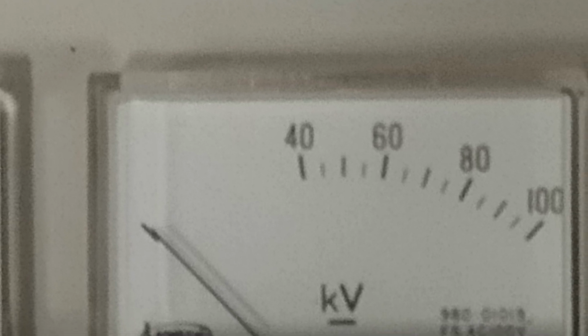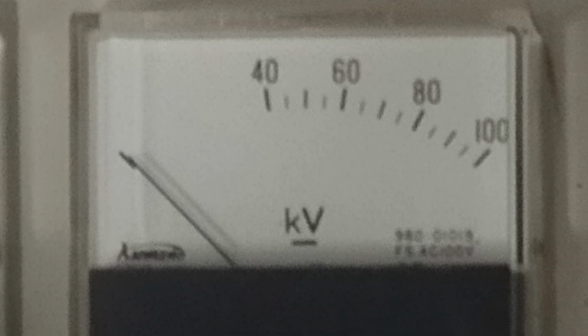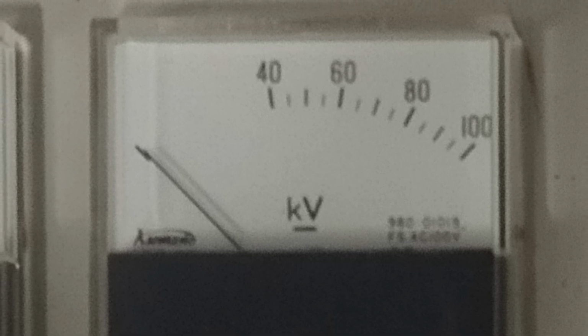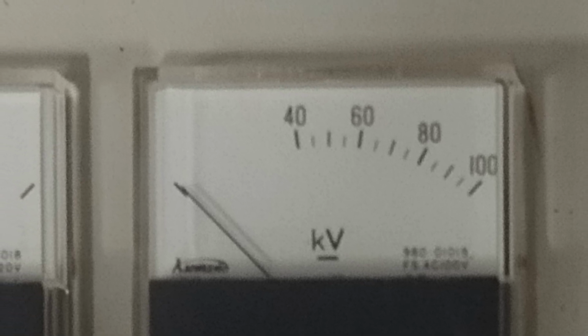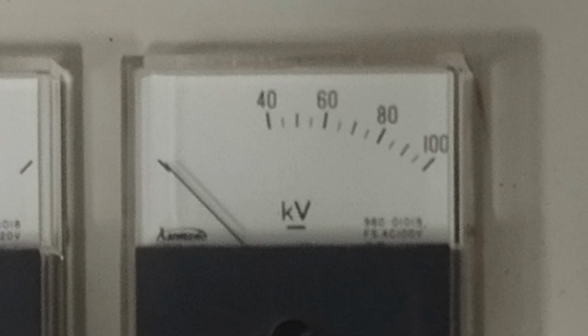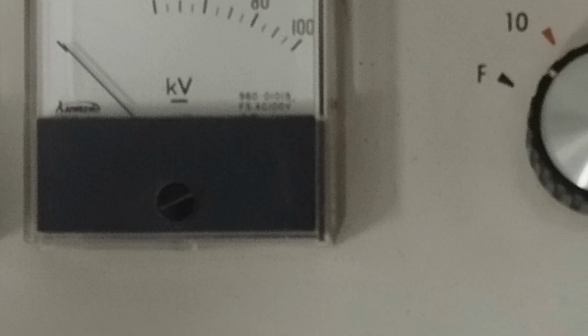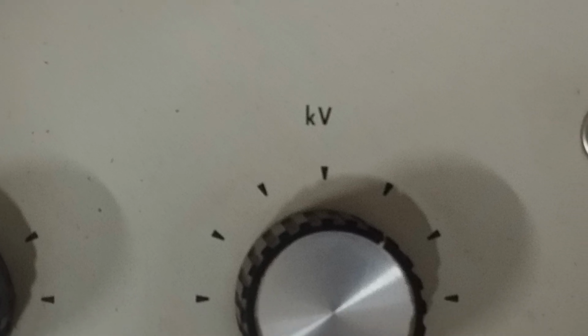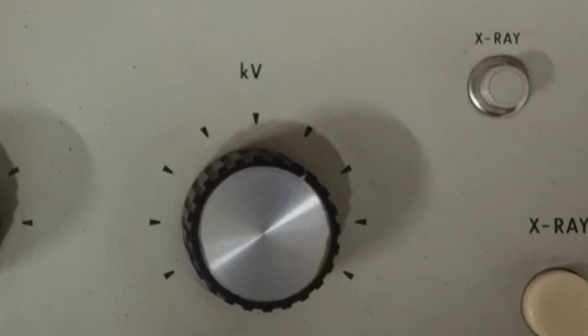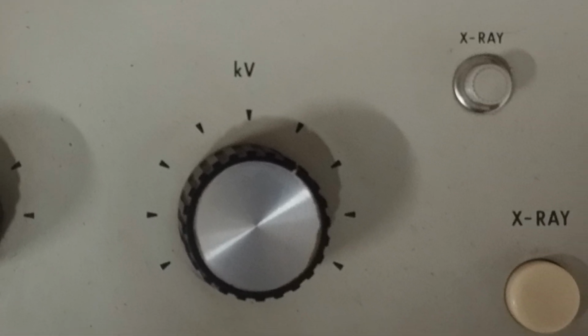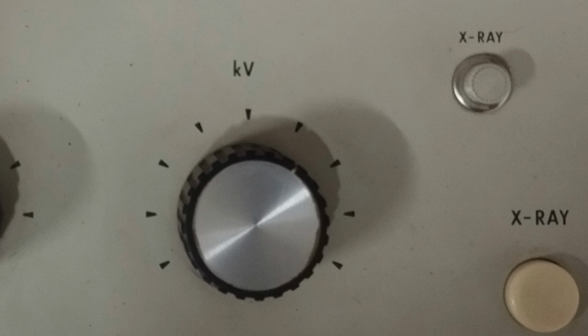Depending on the body part that will be x-rayed, the kV will be adjusted. If you need to see bone, then lower kVs will be used. For soft tissue, higher kVs will be used. So for your hand, you will use something like 50 kV. And then to see your lungs, you will use 100 kV. To look at your abdomen, you will use something in between.